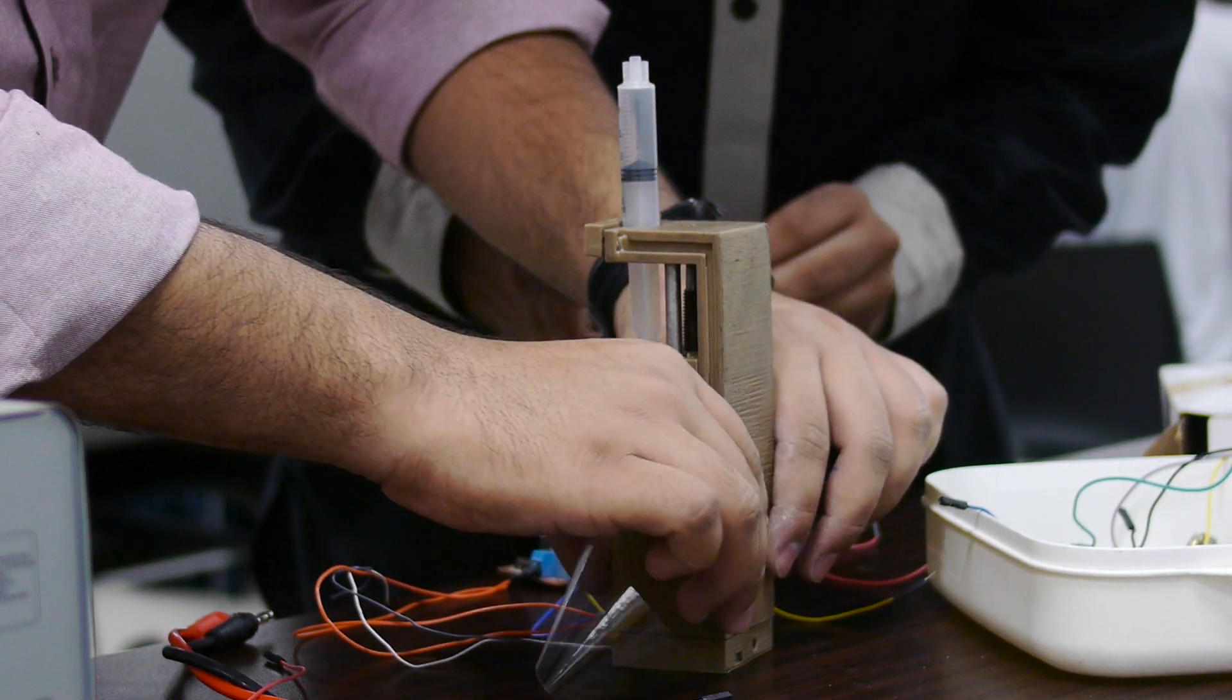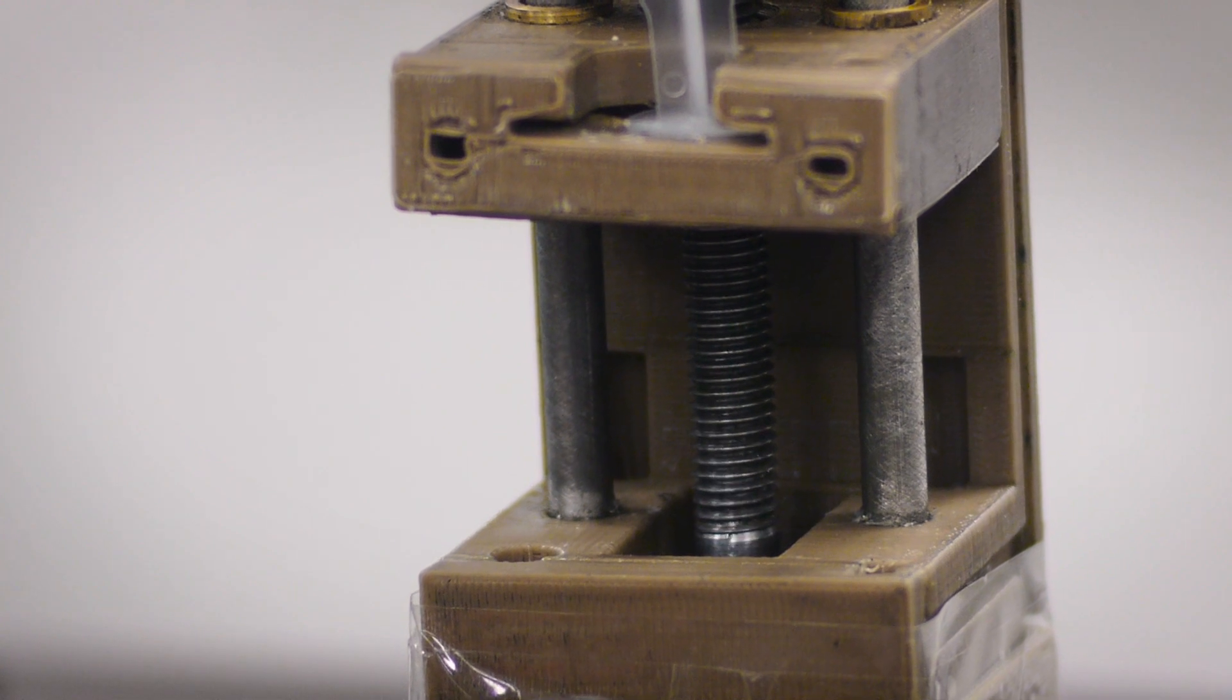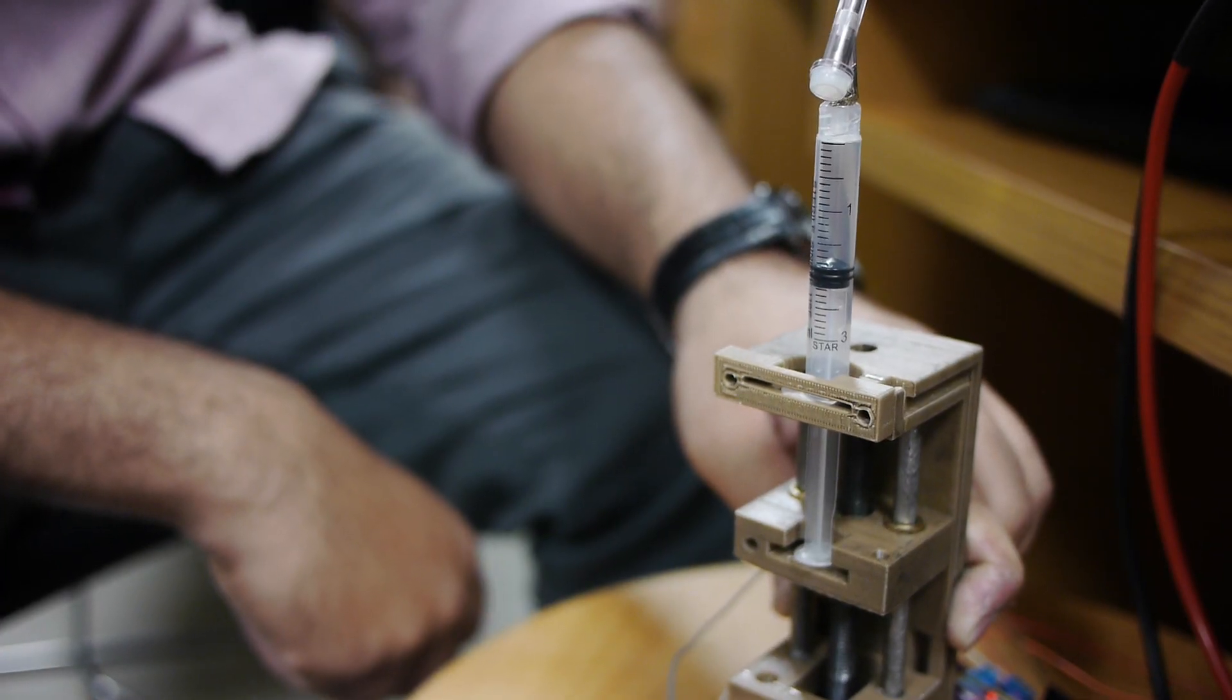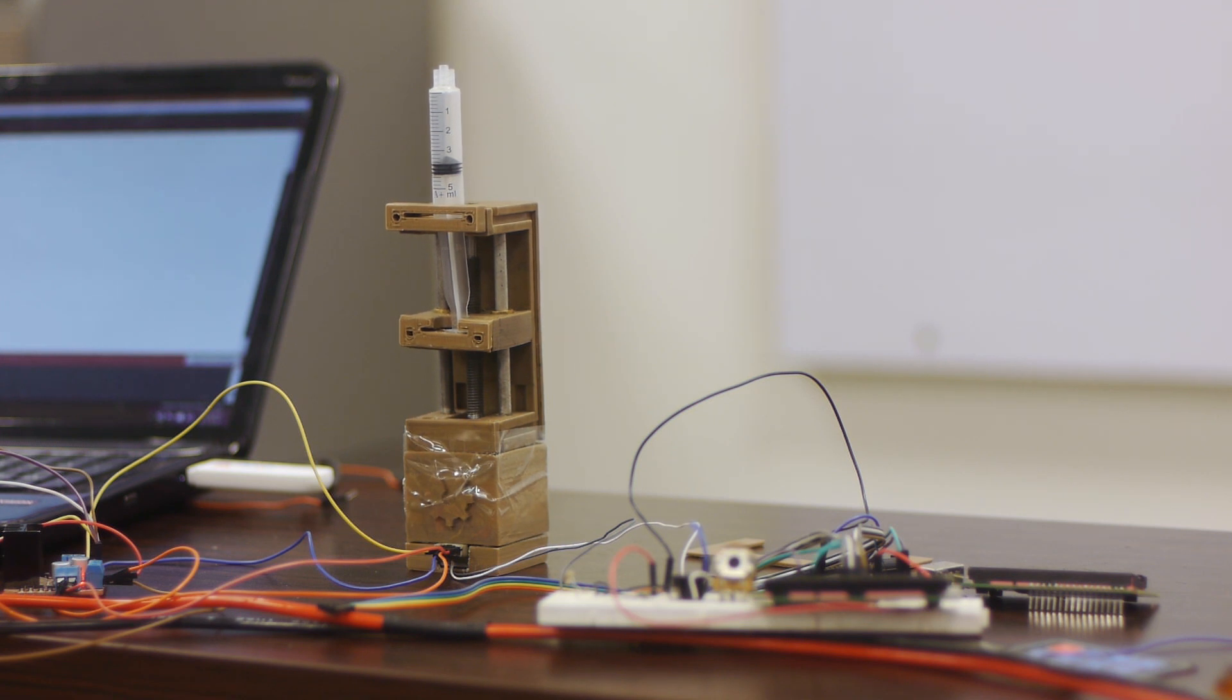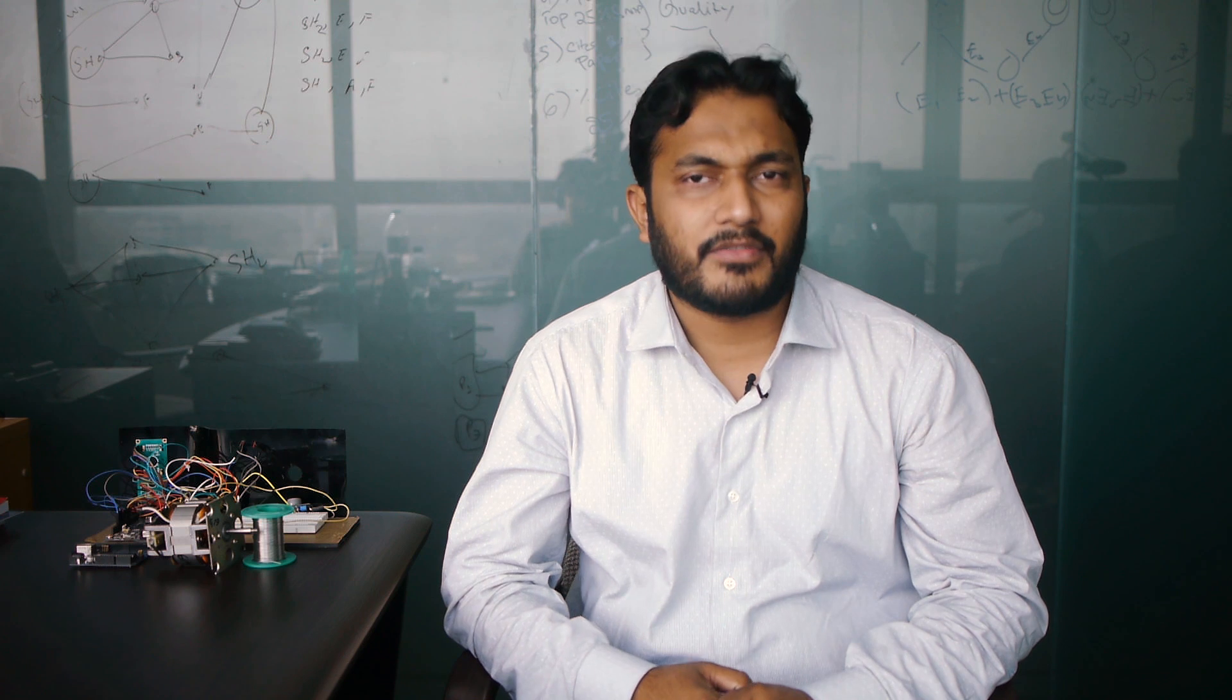Another medical product that we have successfully tested is an infusion pump. Its basic function is to administer drugs at a rate lower than 0.1 milliliter per hour to patients. The current market price for infusion pumps is 100 to 125,000 Pakistani rupees. Our pump designed locally will cost only 15,000 rupees.